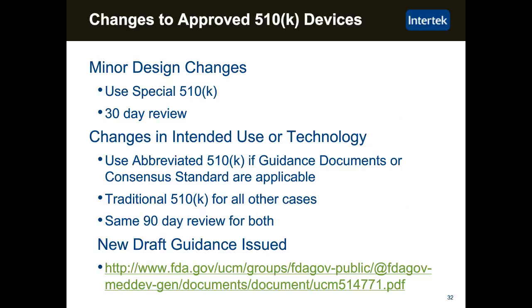So for changes to an approved 510K device, a minor design change, you could use the special 510K approach, and that requires a 30-day review. Any changes in the intended use or the technology of the device may allow the use of an abbreviated 510K if there are guidance documents, which are the special controls or consensus standards that are also considered the special controls for that type of device. Otherwise, a traditional 510K would be required for those changes, and you're into the same 90-day review for both.